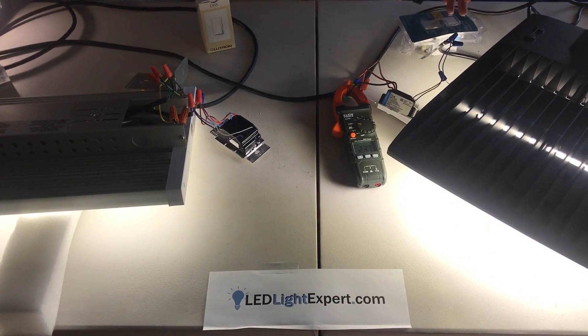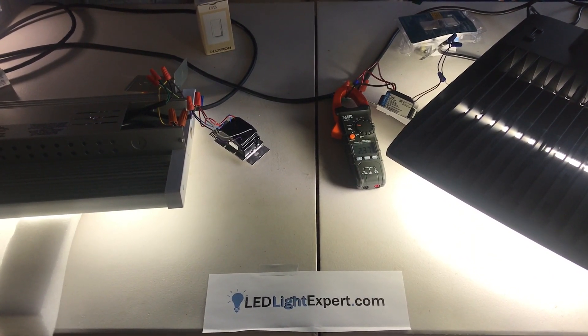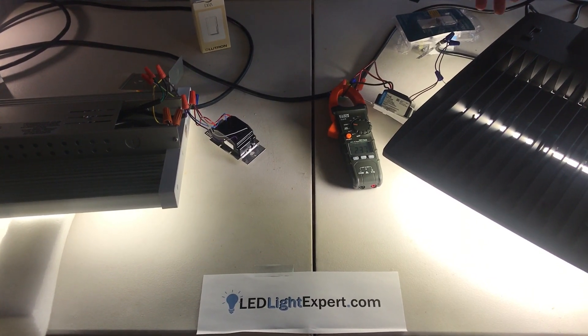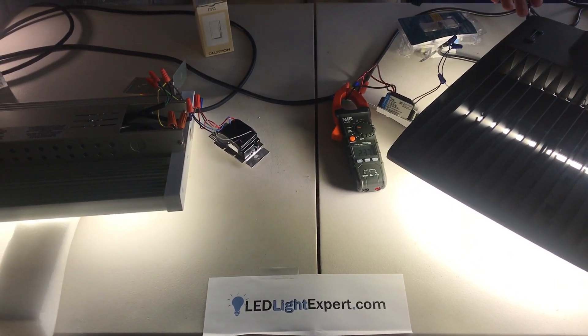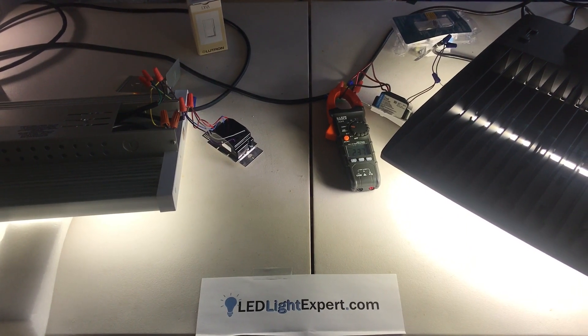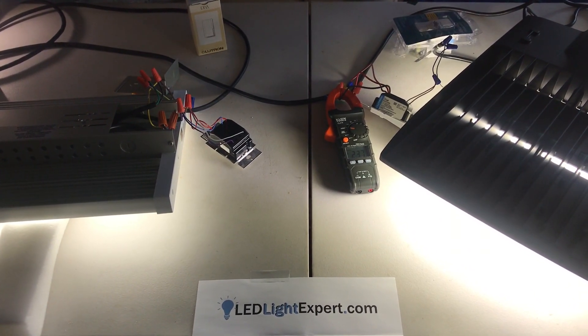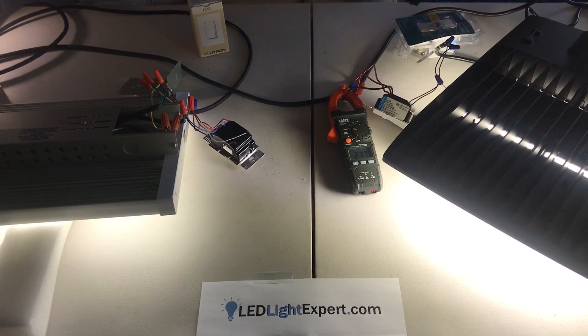If the light has a 10 volt signal, it goes to full brightness. If the light has a 5 volt signal, it goes to 50% brightness. That's why it's called 0 to 10, because of that control. Very simple but elegant system and it works very well.